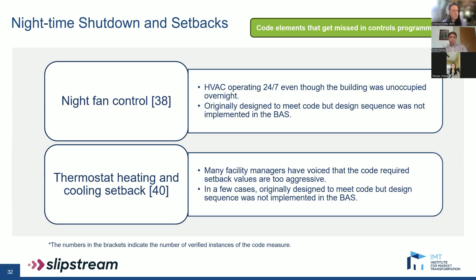For thermostat setbacks, one thing we have been hearing pretty frequently was that the code required setback values were just too aggressive. We've heard that many facility managers felt that their systems could not bounce back to their set points in time for morning occupancy from setbacks as aggressive as what was required. And in a few cases, this was originally designed to meet code, but the design sequence either didn't make it into the BAS programming or was changed by the building operator after occupancy.